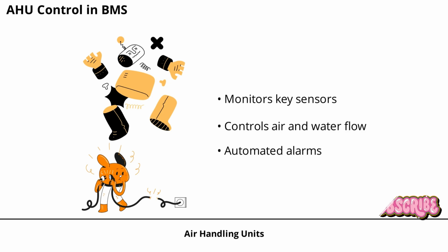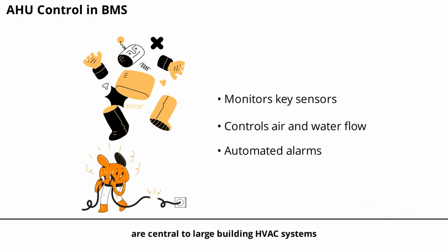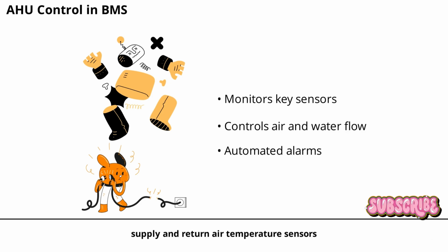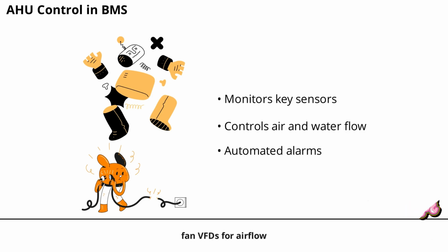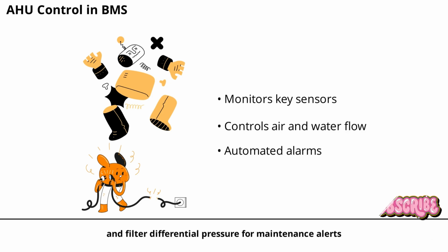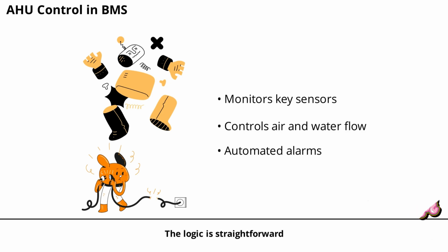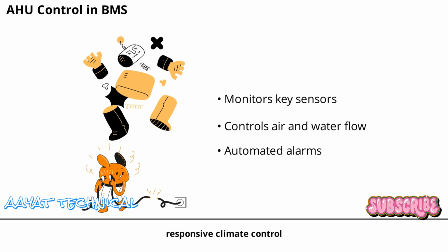Air handling units, or AHUs, are central to large building HVAC systems. BMS monitors and controls key points: supply and return air temperature sensors, CO2 sensors for demand control ventilation, chilled water valves for cooling, damper actuators for air mixing, fan VFDs for airflow, and filter differential pressure for maintenance alerts. The logic is straightforward. If room temperature rises above set point, open the chilled water valve. If CO2 exceeds 800 ppm, open the fresh air damper. If supply air temperature is too high, trigger an alarm. This ensures precise, responsive climate control.